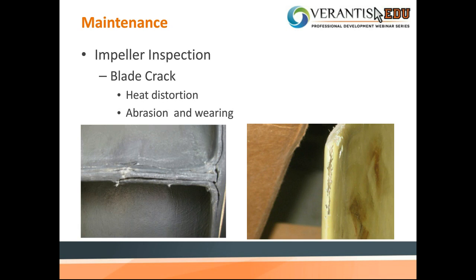So this photo shows some blade cracking, and this has been caused by probably a couple different things. There's heat distortion as well as abrasion and wear that can cause these types of things. So in the picture on the left, you'll see where it's actually started to delaminate, where the different layers of fiberglass have broken apart from each other. Whereas the picture on the right shows more of an abrasion wear situation where it's slowly getting into the surface of the impeller.